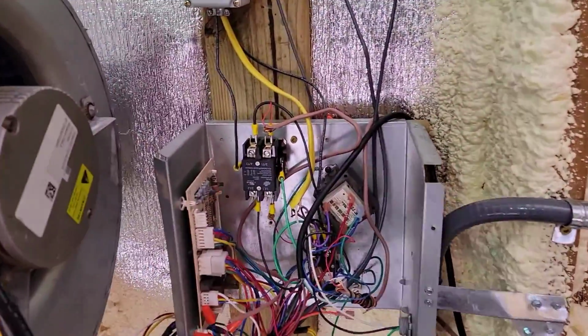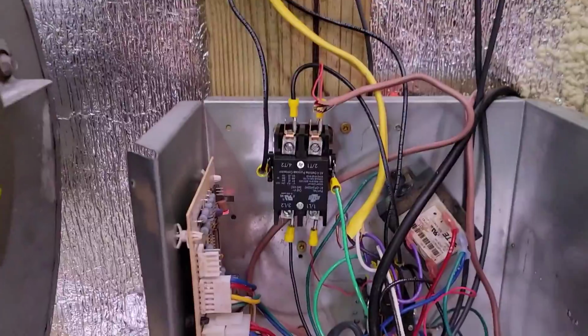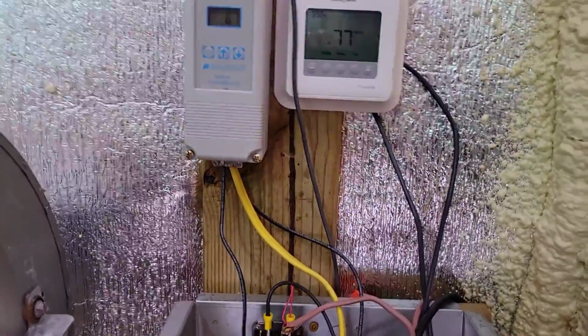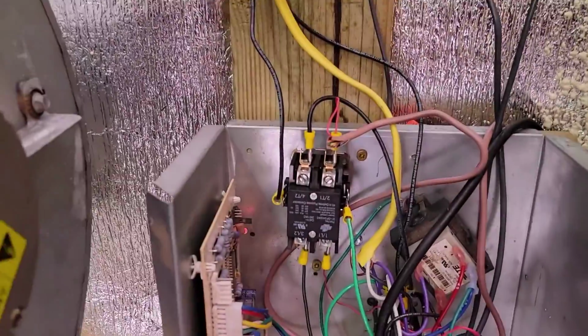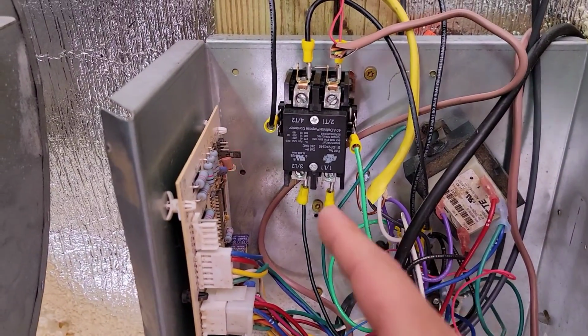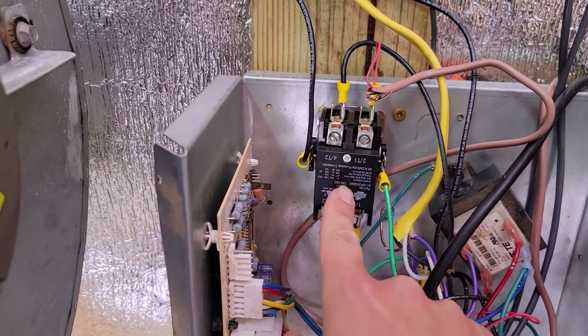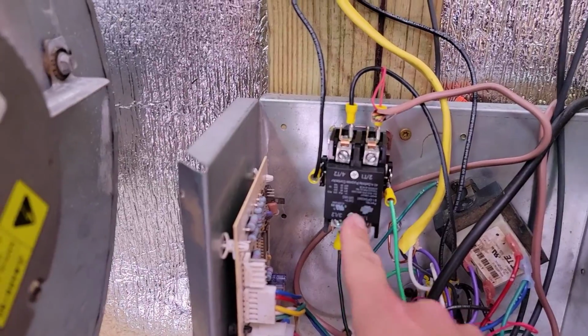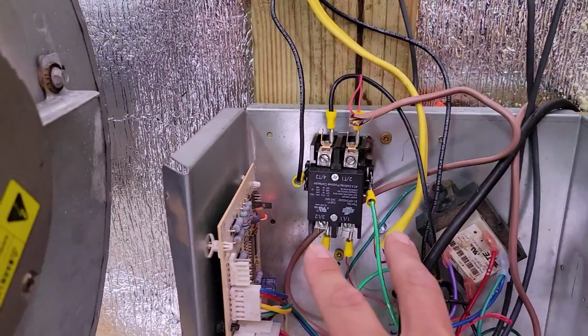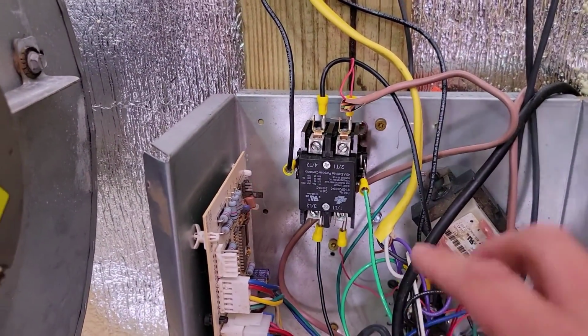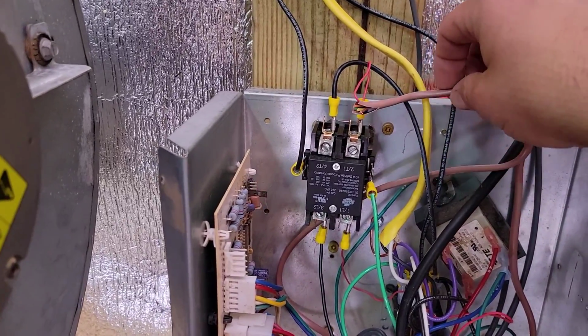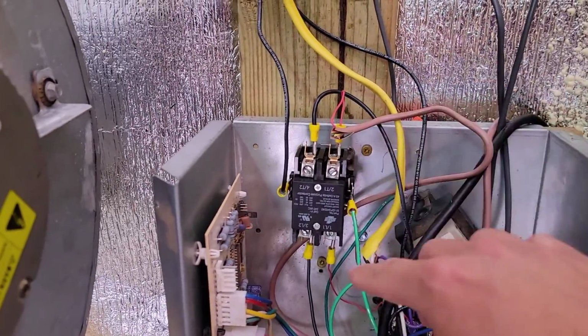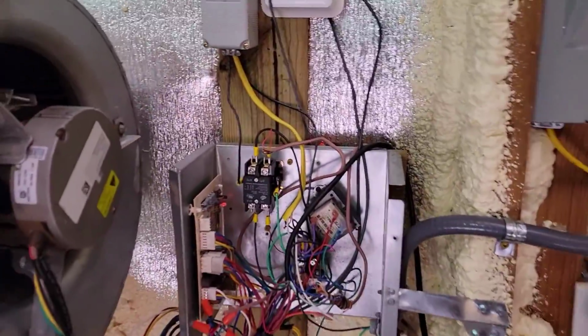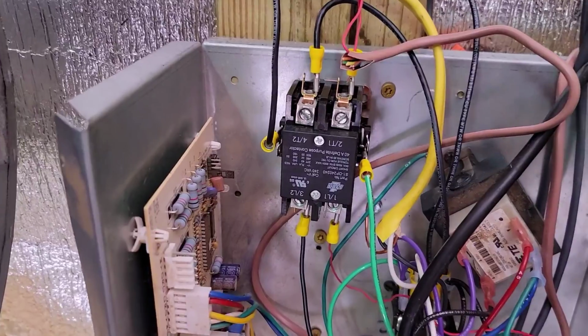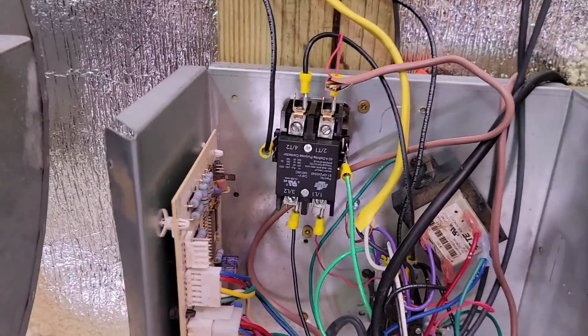24 volt would have been easier, but this was just as easy. So what I did was I broke the contacts, and when it closes the relay, it sends 240 volts to one side of this contactor, because this is a 240 volt coil contactor. When it closes, I've got a thermostat wire here, and this thermostat wire breaks the red to the condenser outside. That condenser calls for the 24 volts and energizes the reversing valve, and it runs in cooling.